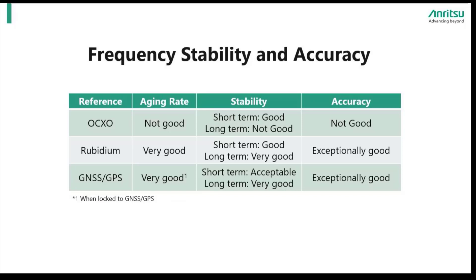The next natural question should be: what causes instruments to behave in any of the scenarios we have just shared? For signal generators, most of the behavior we have just explored would be attributed to the frequency reference. To make this point clear, we have a table that shows three references, aging rate contributions, and their respective stability and accuracy qualities.